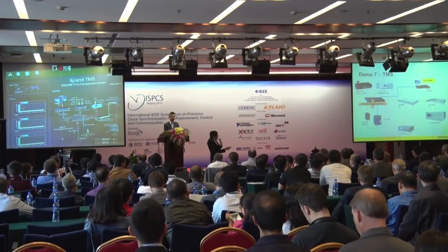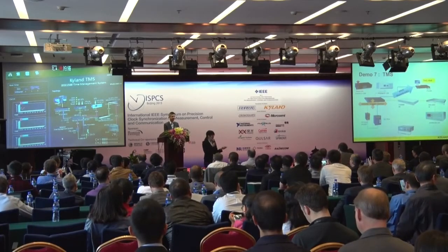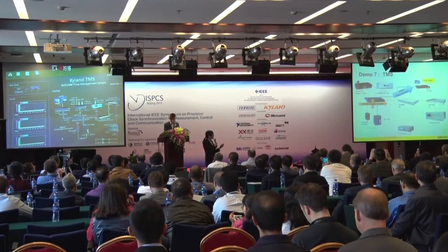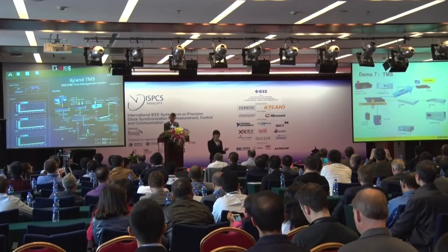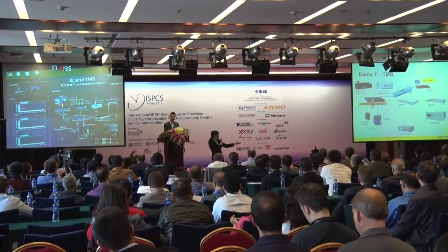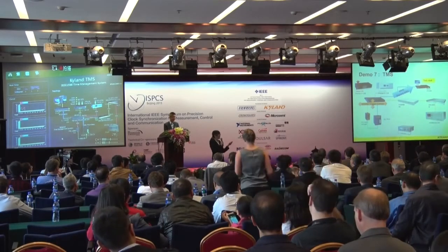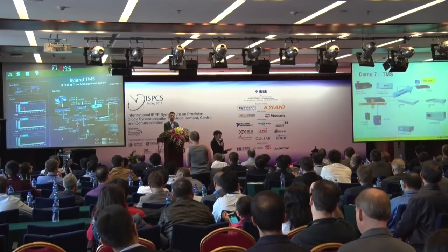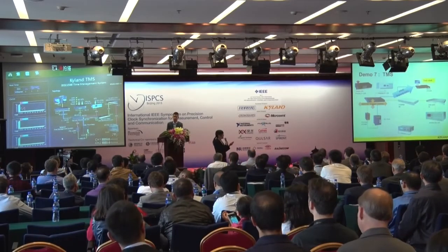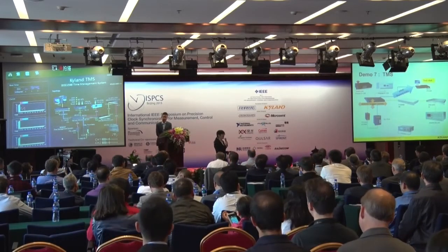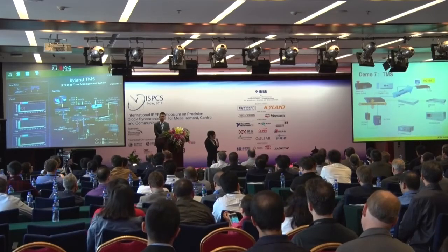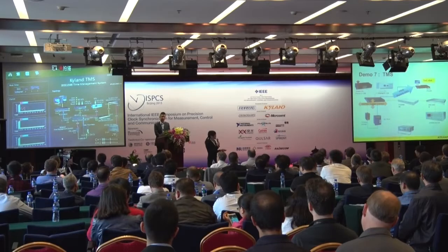So anyone who subscribes to this information can send out the MMS report with SOE information inside. We are using a data analyzer to concentrate and analyze all these MMS reports from the end devices, and we can use an HMI through this data analyzer to track the node time in the system. And that's how this TMS works.